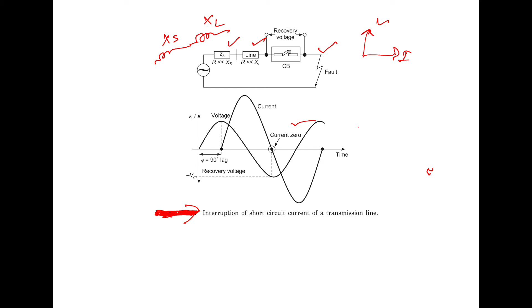So the current lags the voltage by a large angle, about 90 degrees, because we neglect the resistance, as the fault is very near to the circuit breaker and the only impedance is the transmission line and generator impedance. In this case we have assumed that the DC offset in the fault current has died down by the time the interruption takes place.